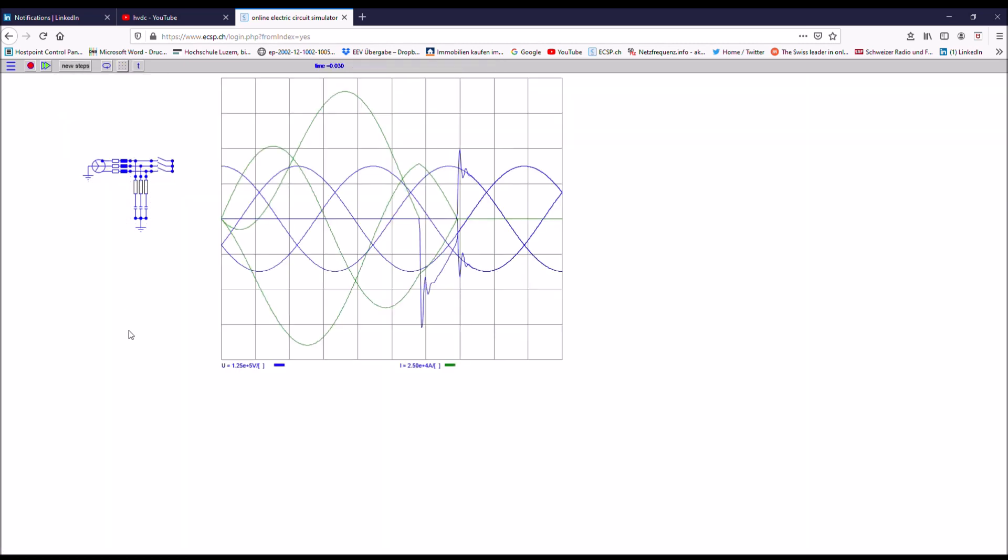Here you can now clearly see that the first TRV is 1.5 times higher. This is due to the fact that the short circuit is not against ground. But it is a non-grounded short circuit just between the individual phases.